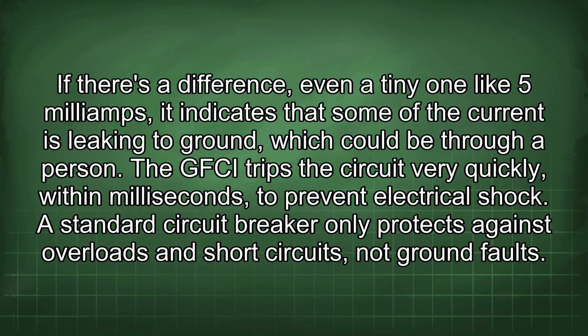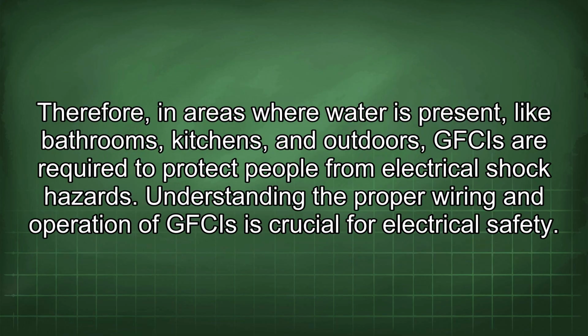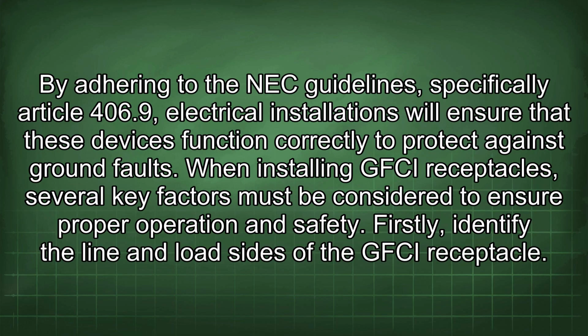A standard circuit breaker only protects against overloads and short circuits, not ground faults. Therefore, in areas where water is present, like bathrooms, kitchens, and outdoors, GFCIs are required to protect people from electrical shock hazards. Understanding the proper wiring and operation of GFCIs is crucial for electrical safety. By adhering to the NEC guidelines, specifically Article 406.9, electrical installations will ensure that these devices function correctly to protect against ground faults. When installing GFCI receptacles, several key factors must be considered to ensure proper operation and safety.